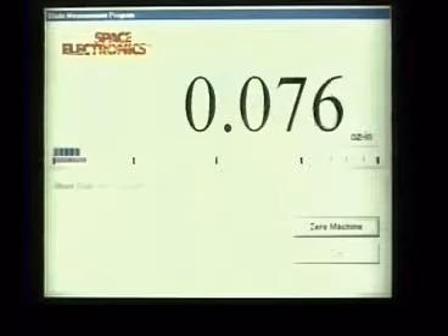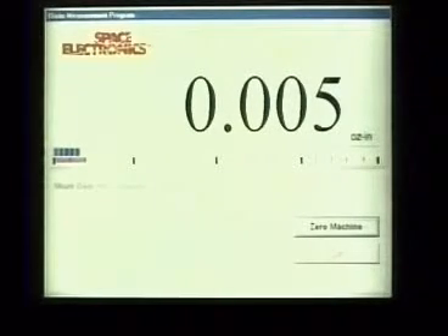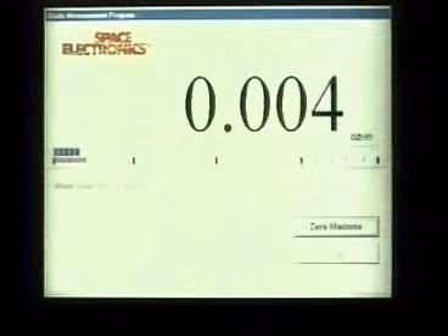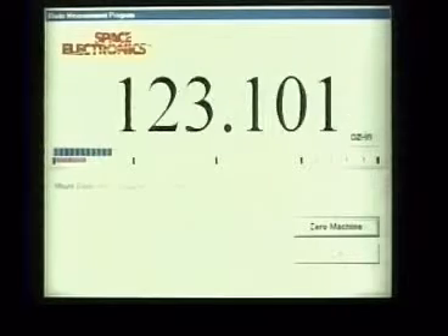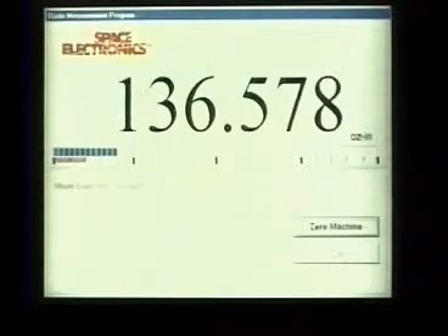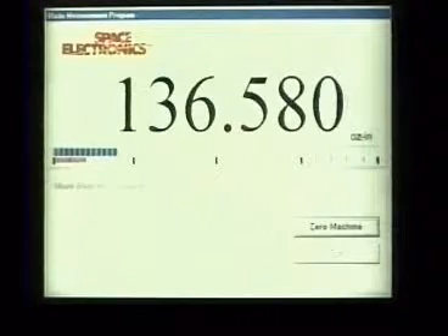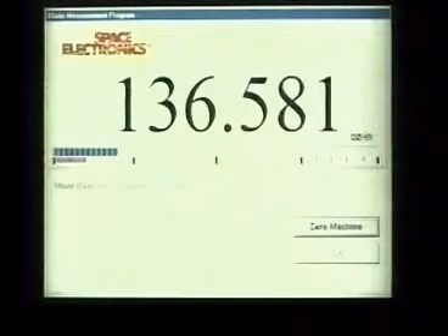But the reading is not exactly valid because the zero point is not right on zero. It's about four thousandths of an ounce inch off. I'll do another measurement. 136.580, so it's changed by two thousandths of an ounce inch. So when we get down into this resolution, now we see some very small effects. If the temperature were to change by a few degrees as we made this measurement, we would see the moment change. And here you can see the machine does drift in the order of one thousandth of an ounce inch.